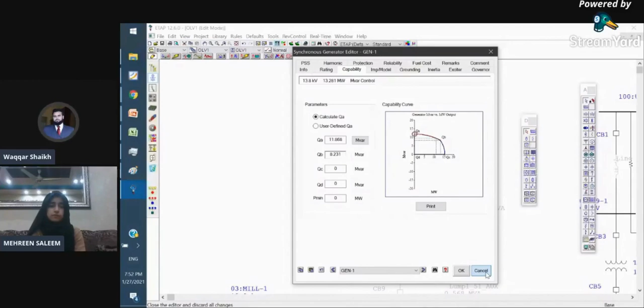Once we have properly created the capability limit of the generator, then in the load flow study, if you go here in the study case editor, it is very important for running the right simulations. You have the option of overexcitation, upper and the critical and the marginal limits, and the underexcitation. By giving the ranges from here, it will check the actual outward active power from the generator. If that active power is more than the capability limit, as ETAP took the inputs in the beginning, it will give you an overloading alert.